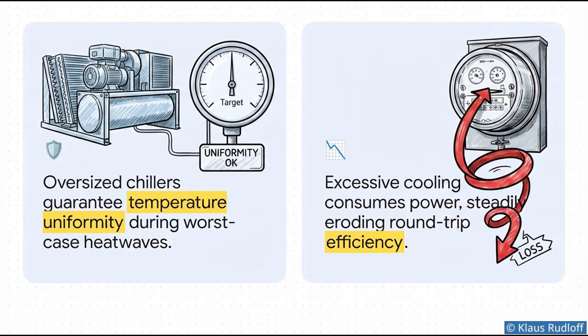It prevents accelerated cell degradation during worst-case heat waves — you need your battery cells to survive a prolonged heat wave without catching fire or degrading prematurely. But asset optimizers point out that this excessive cooling constantly consumes power during normal partial load operations, meaning you're paying a massive continuous efficiency penalty for a worst-case scenario that almost never happens.